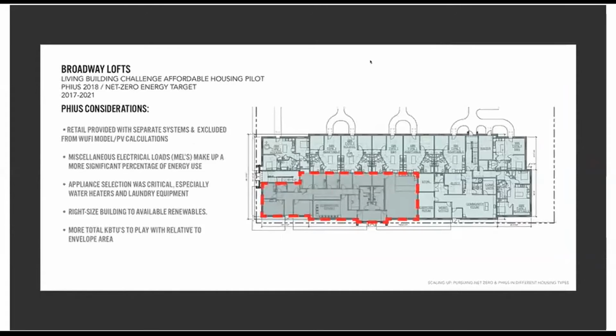This was our first time working on a true multifamily mixed-use passive house project. We registered it under the 2018 PHIUS certification, which uses the newer multifamily calculators for several items, including the overall calculator that determines target values for heating and cooling loads. The calculator used to just take into account the location of the project, but now adjusts targets based on your interior conditioned floor area, which works in your favor with multifamily because it also accounts for the number of occupants in the building, making your targets a little more feasible to hit.